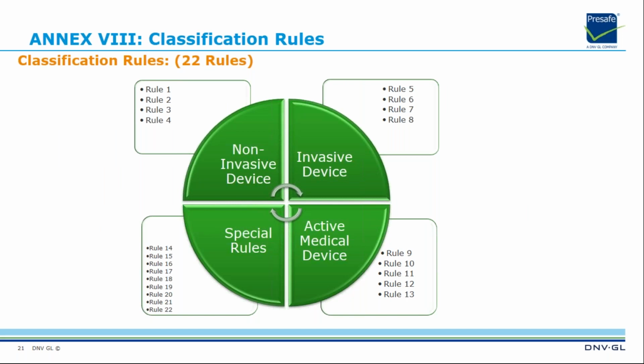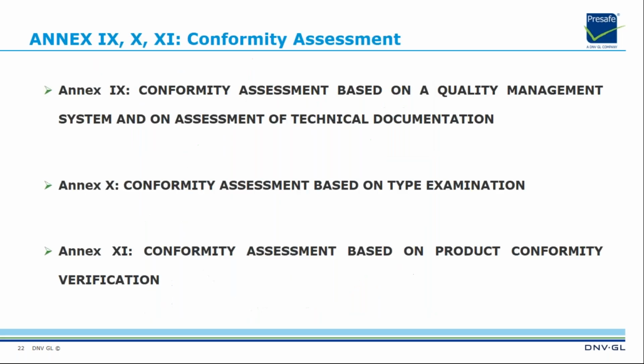Manufacturers of medical devices should carefully examine the MDR classification rules in Annex 8 to determine whether new conformity assessment rules are now applicable to their products or not. If so, they should engage their notified body where necessary and take steps to evaluate the necessary timescales involved in implementing this change. In some cases where reclassification has occurred, this may be the first time that such relationships and agreements with a notified body have been required.